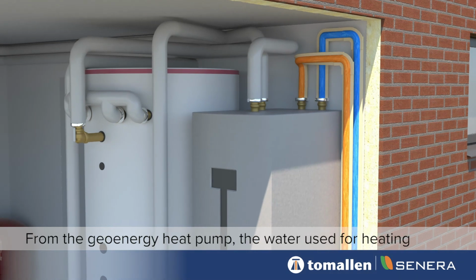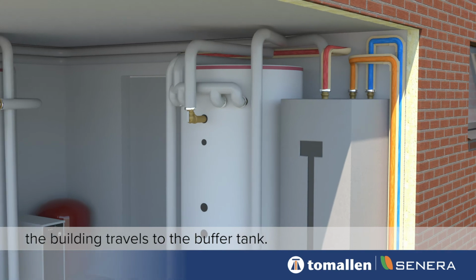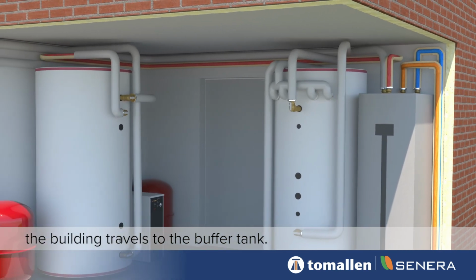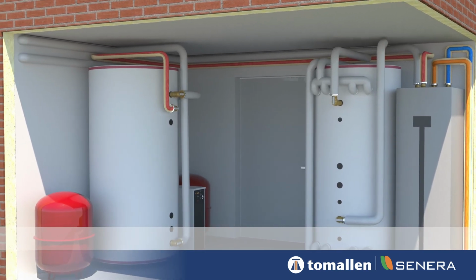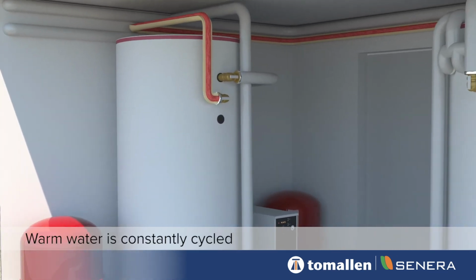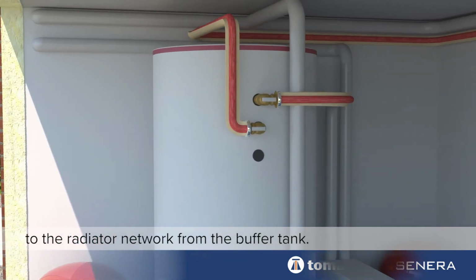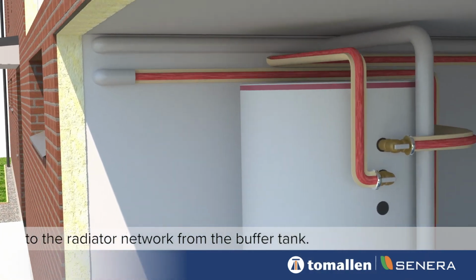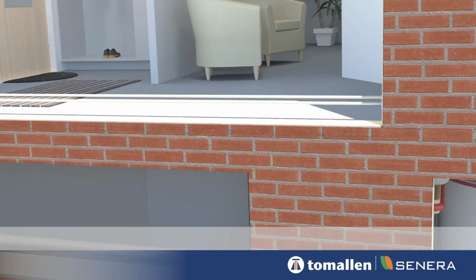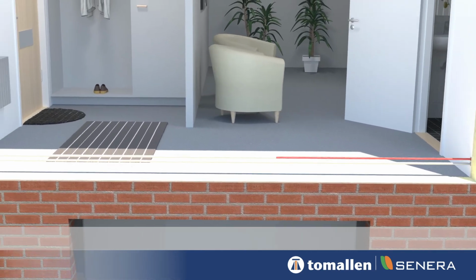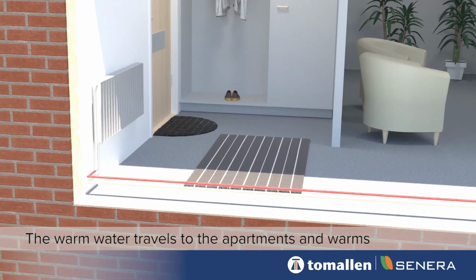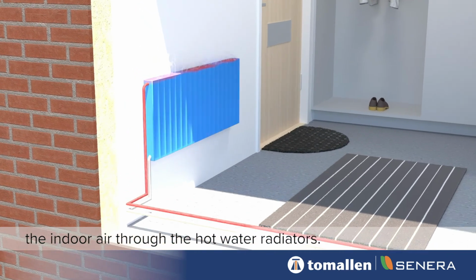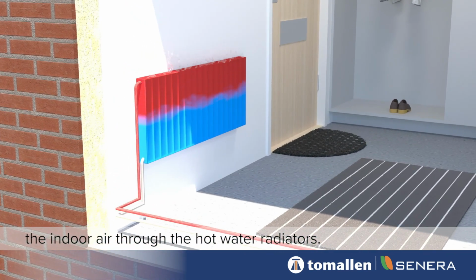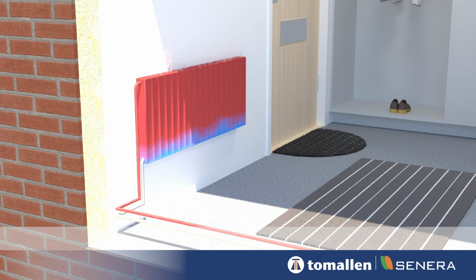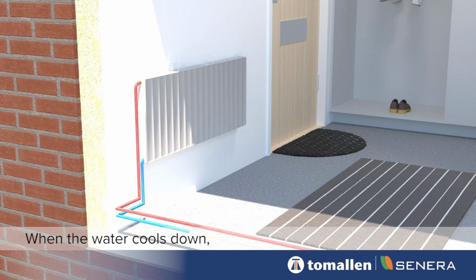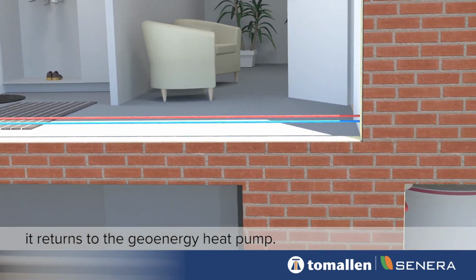From the geoenergy heat pump, the water used for heating the building travels to the buffer tank. Warm water is constantly cycled to the radiator network from the buffer tank. The warm water travels to the apartments and warms the indoor air through the hot water radiators. When the water cools down, it returns to the geoenergy heat pump.